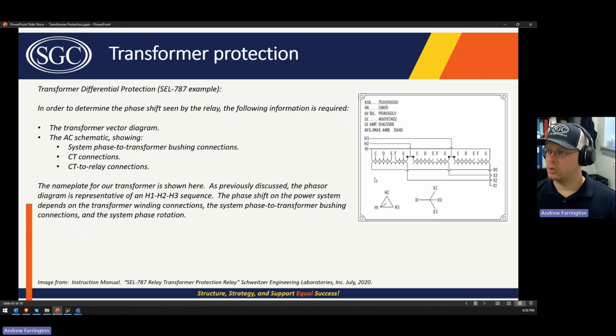All right, so we know from our previous class that this is a DY1 transformer, because if you brought this X1 phasor over to this, the X1 phasor would plot out here at 180 degrees, right? Because of the 0, 90, 180. It would plot right over here. And so if you had a counterclockwise rotation, H1 would show up before X1 by 30 degrees. So there's a 30-degree phase shift. The Y winding is lagging by 30 degrees. So it's a DY1 transformer.